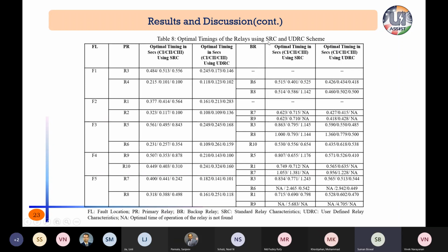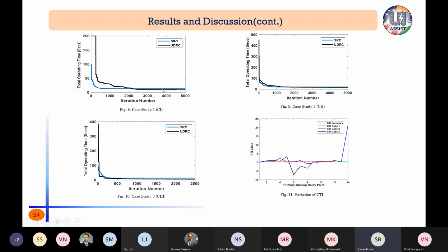Compared this standard relay characteristic with UDRC, if we observe the third and fourth columns, the primary operating time is 0.4. So better operating time is obtained in the UDRC scheme, as we are controlling more variables, more relay parameters. In all the cases, the primary relay operational time as a constant is set to 0.1. So in all the cases, the time of operation is more than 0.1 or nearer to 0.1. So better improved performance is obtained, not only in primary relays and backup, ensuring the coordination criteria holds properly as well. And these are the same converging characteristics of the 3 case studies mentioned.